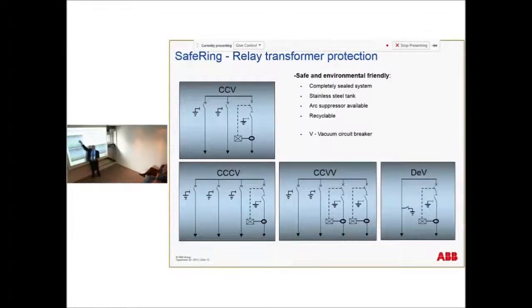We have also the same where you can use a vacuum circuit breaker instead of a fuse. You can use a vacuum circuit breaker with an electronic relay with pickup of current here with the CTs. Then you feed the relay and you open the breaker. This is if you have a high rating, from 1600 kVA, we recommend to use a vacuum circuit breaker. But also you will see that more and more relays are advanced, where you can have this also for self-powered relay. So this V is for the vacuum circuit breaker, and in here there's a vacuum bottle. Later on I made quite a lot of pictures from the factory so that you can see how this looks also inside.